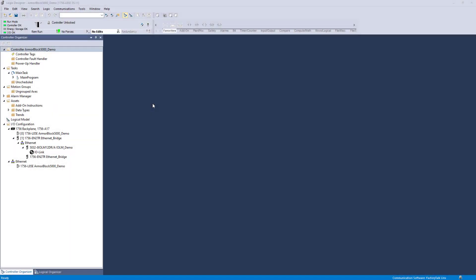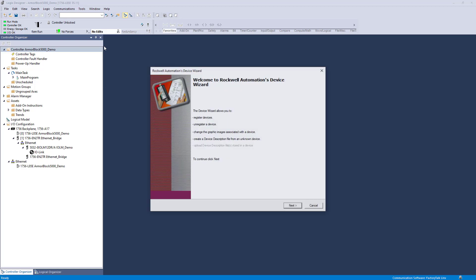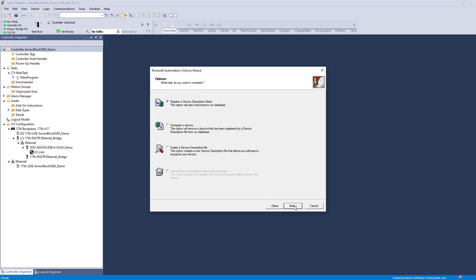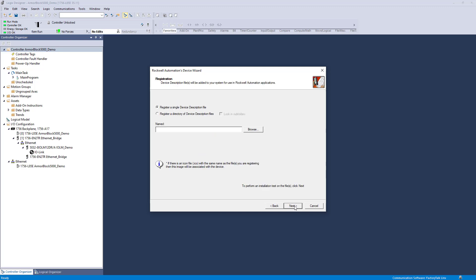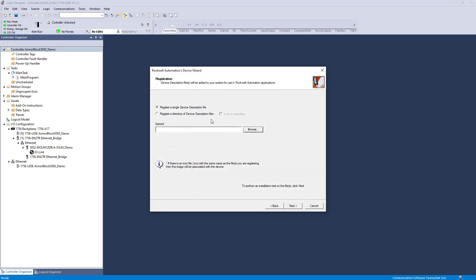Once the IODD file is obtained, it must be registered. To do so, open the Studio 5000 Logix Designer application and select EDS Hardware Installation Tool from the Tools menu. Browse to the IODD file that you need and complete the Device Wizard prompts to register the file.